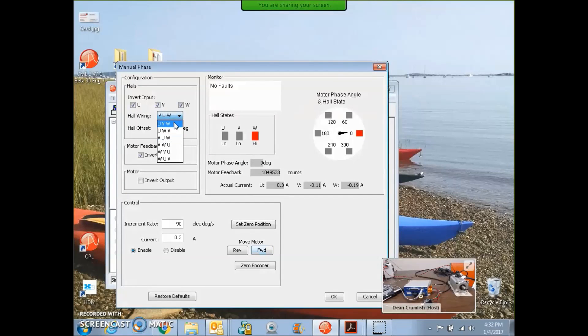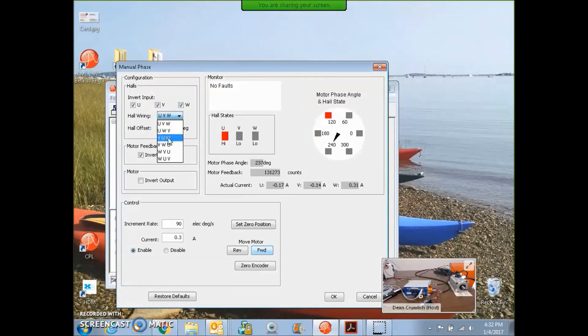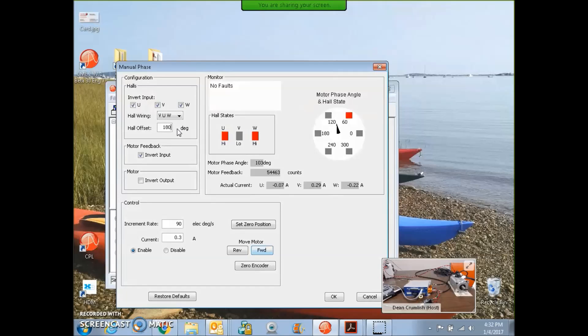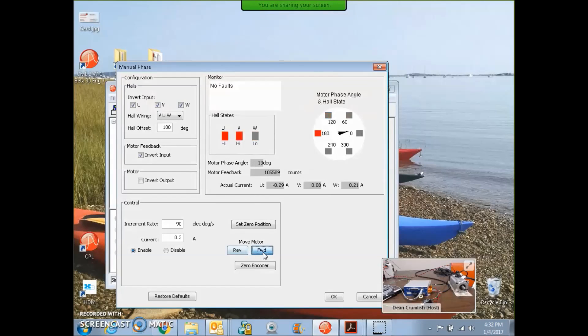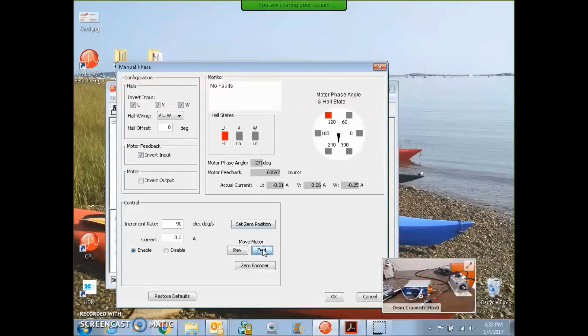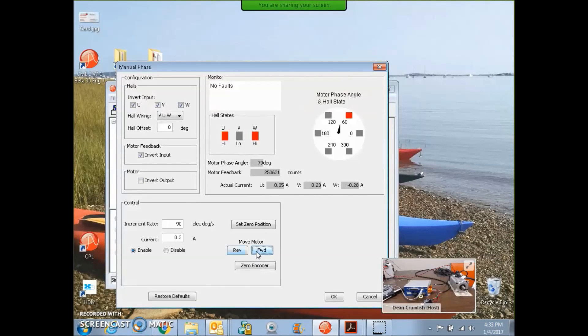If you had the wrong Hall wiring, it just wouldn't look right. You pick the wiring to get it to go the right direction, and if you got a lead or a lag, you can compensate that with the Hall offset. This is 180 degrees out of phase here. You can also change the count direction to make counts go up when you go forward. Counts must go up when you go forward, and you can change the motor direction if you want to go the other way, but if you change the motor direction, then you'll have to change the count direction. They go hand in hand.